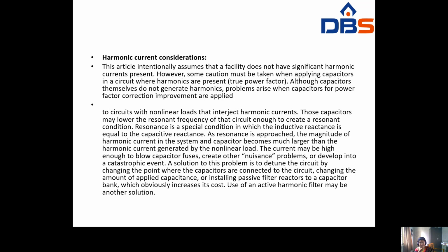That current will cause the capacitor fuses to blow. Nuisance problems can develop into a catastrophic event, and at that time the entire system may be damaged. A solution to this problem is to detune the circuit by changing the point where the capacitors are connected to the circuit.